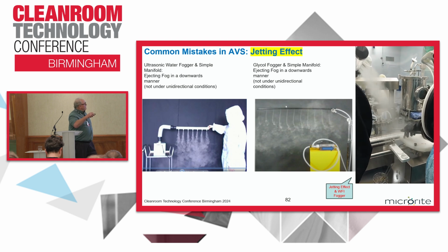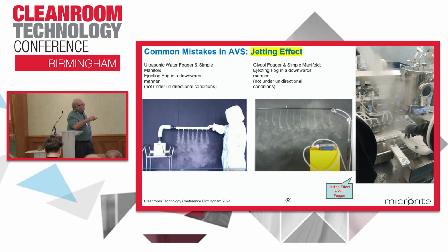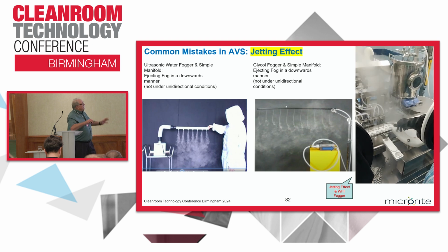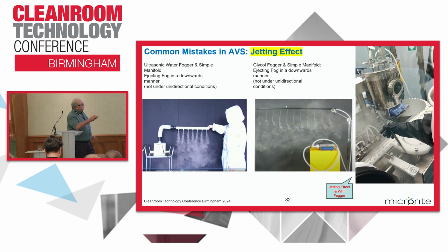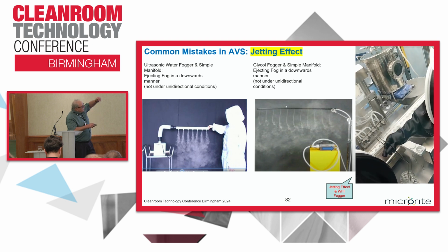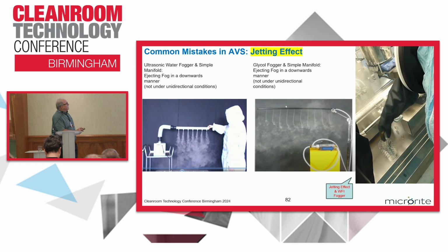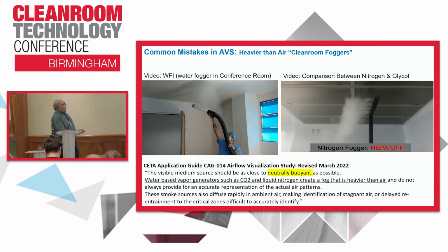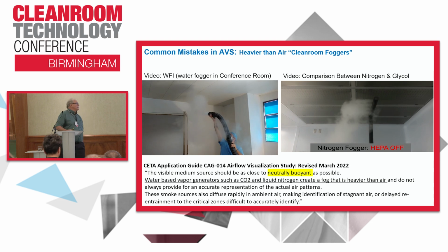Yet the smoke is being injected downward. Same over here. It's downward, and you can see it loses its energy and starts to spread out in the room. And here's a video sent to me by a good friend of mine, of smoke studies, and here he's ejecting the smoke directly over the operator, and it's going in a downwards motion. It's one common mistake.